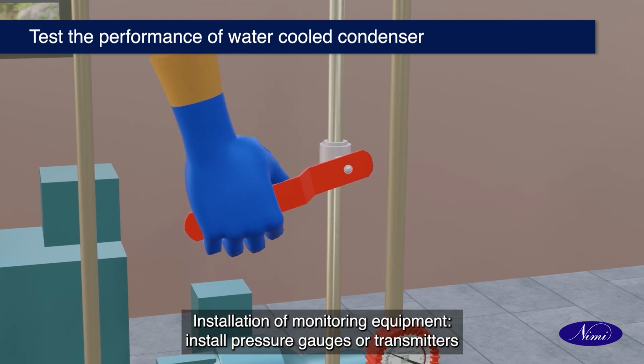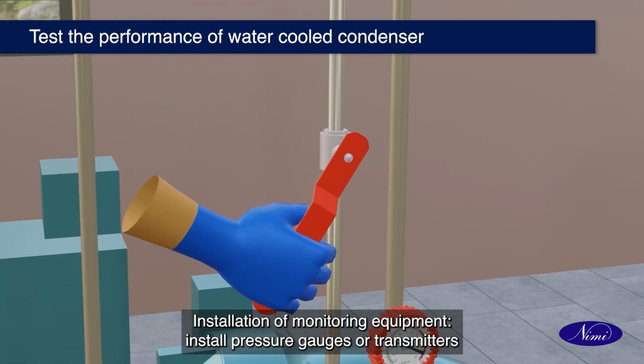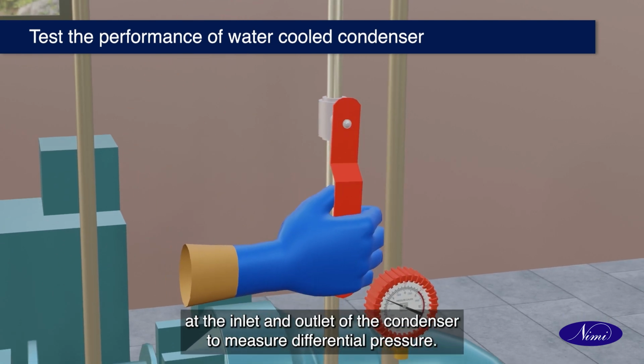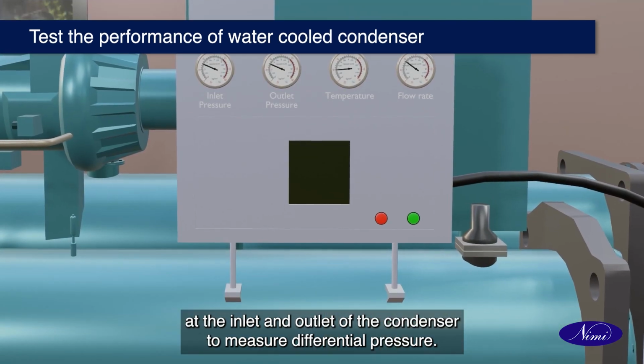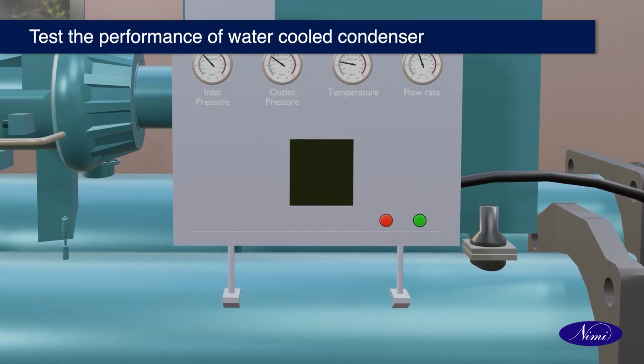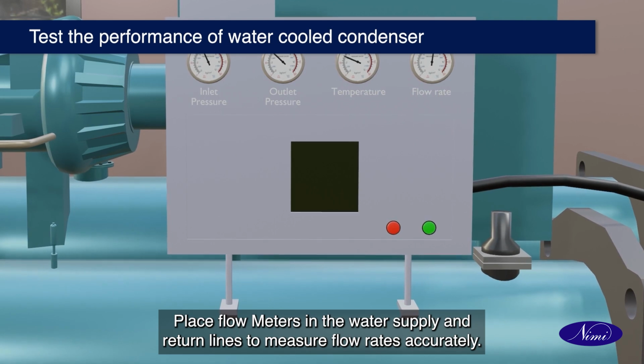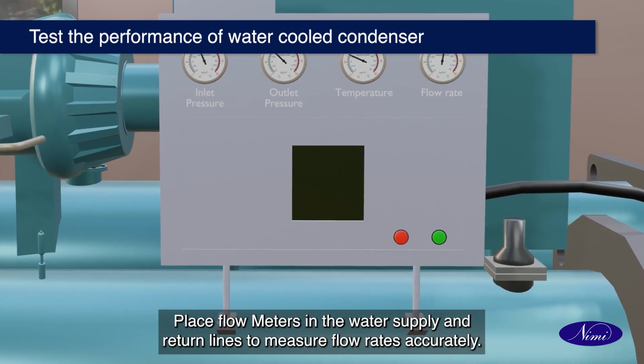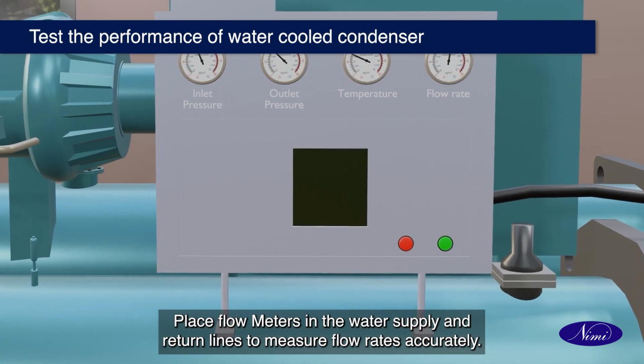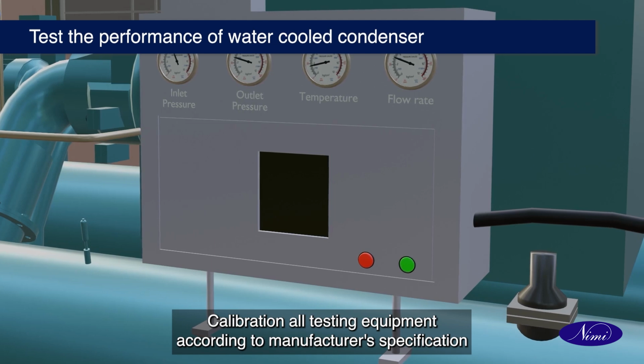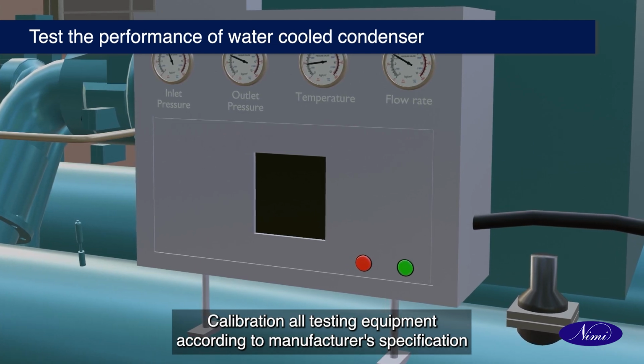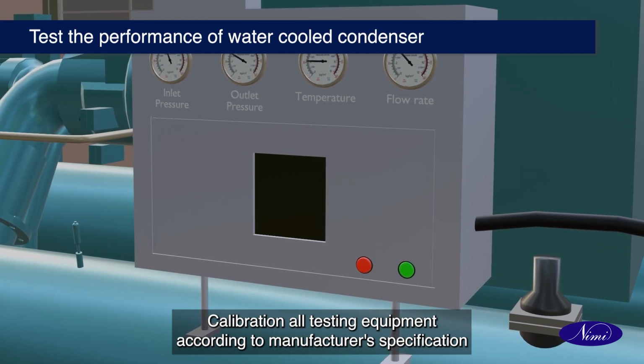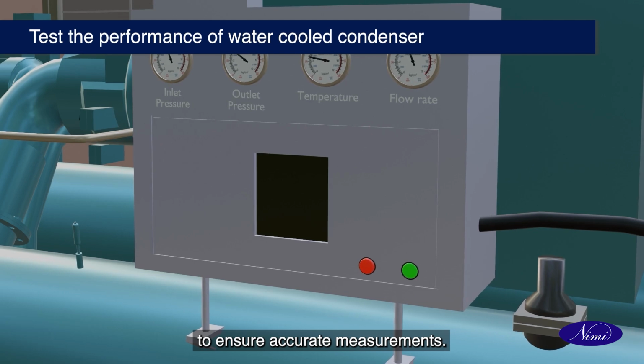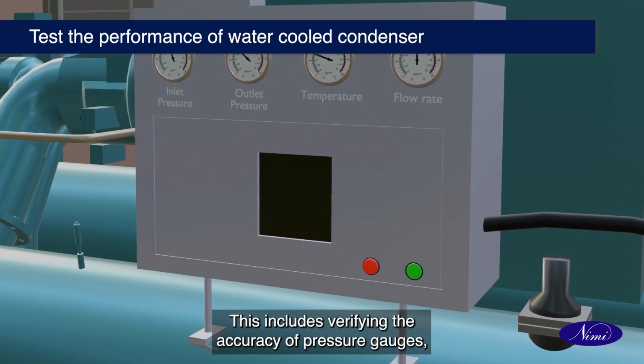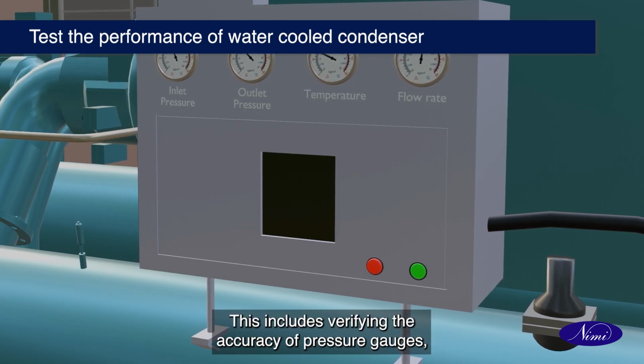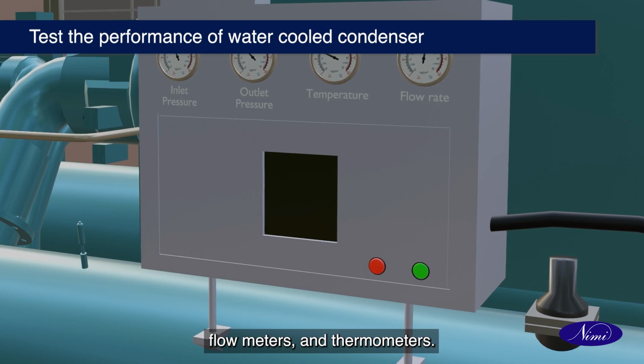Installation of monitoring equipment. Install pressure gauges or transmitters at the inlet and outlet of the condenser to measure differential pressure. Place flow meters in the water supply and return lines to measure flow rates accurately. Calibration. Calibrate all testing equipment according to manufacturer specification to ensure accurate measurements. This includes verifying the accuracy of pressure gauges, flow meters, and thermometers.